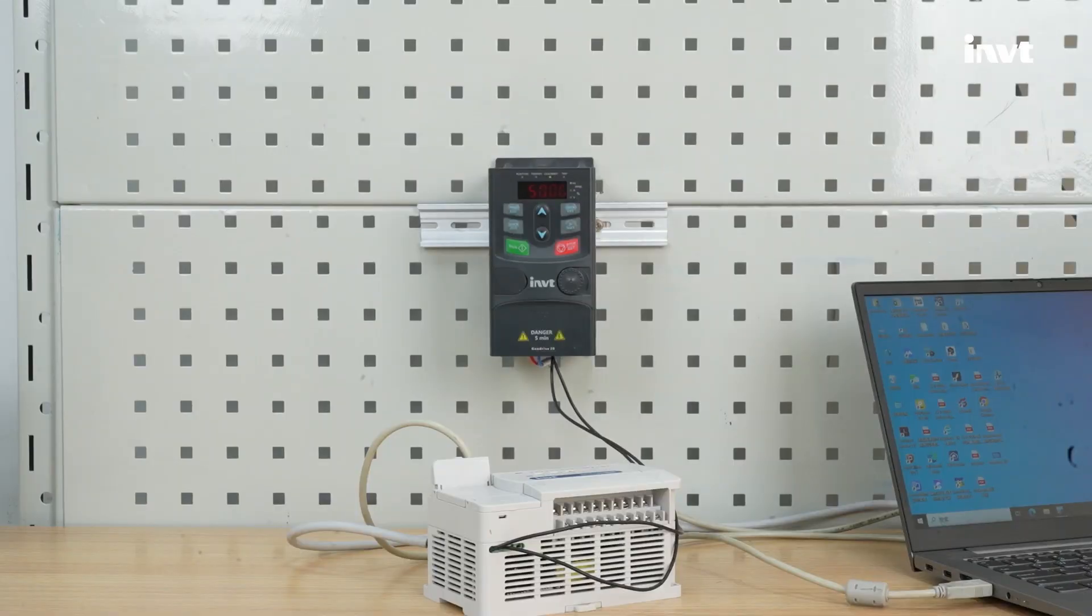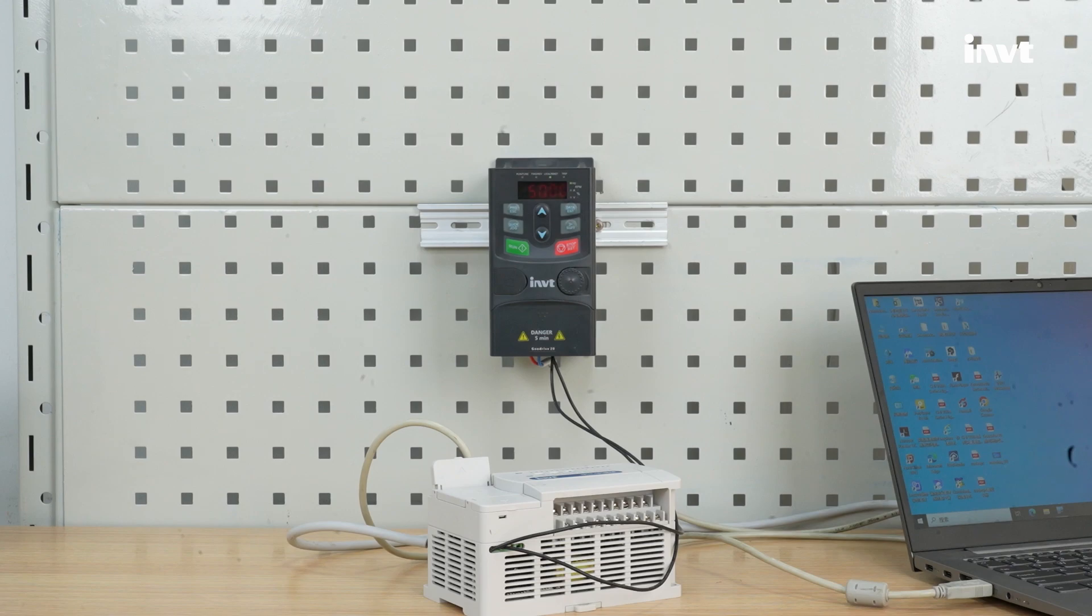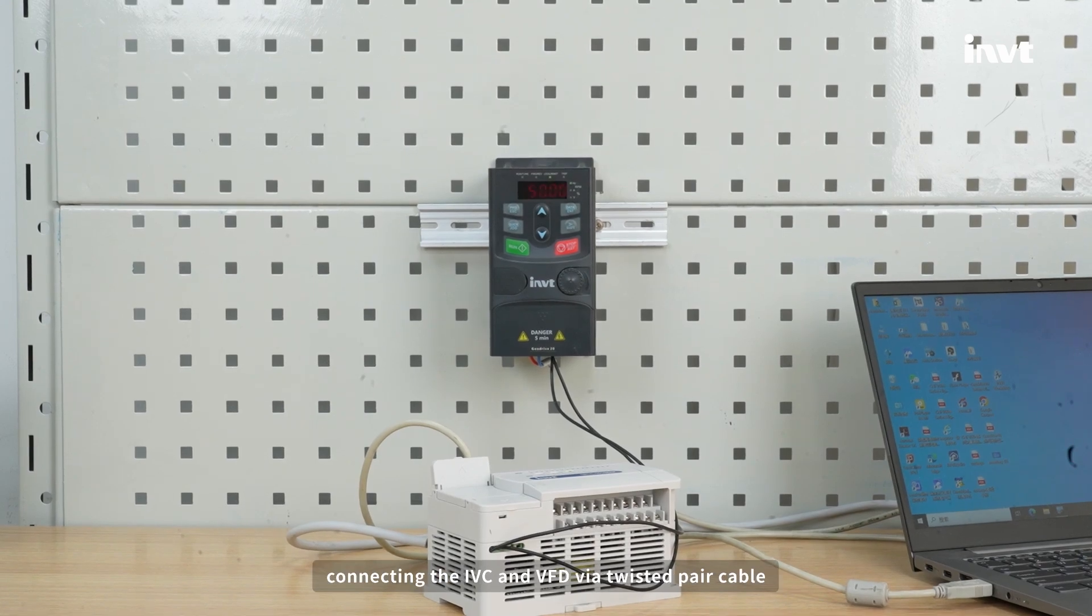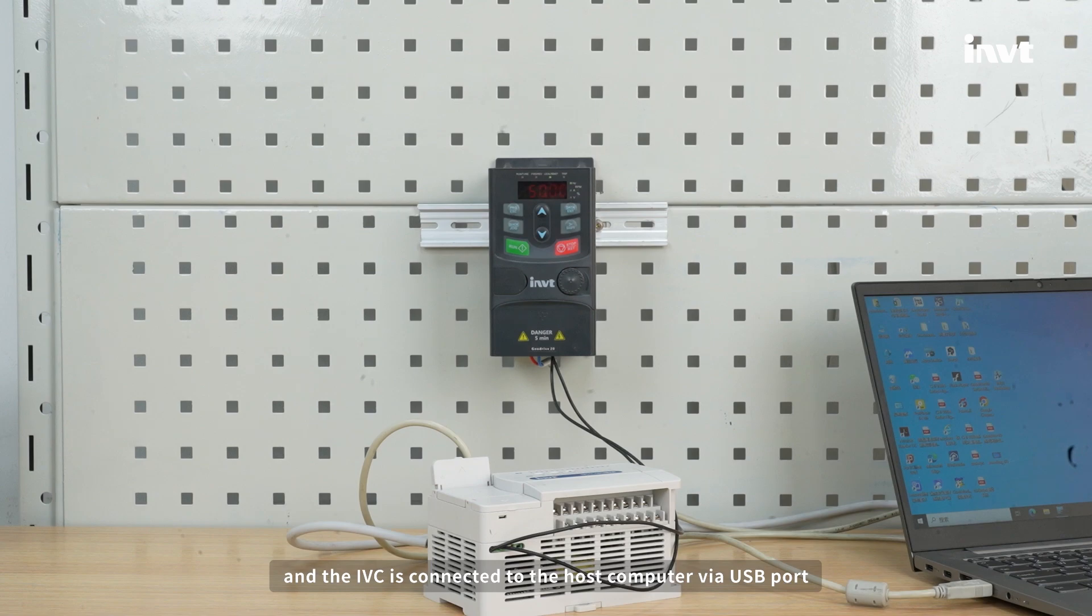How to use INVT PLC to control GD20EU. The device uses RS-485 communication, connecting the IVC and VFD via twisted pair cable, and the IVC is connected to the host computer via USB port.